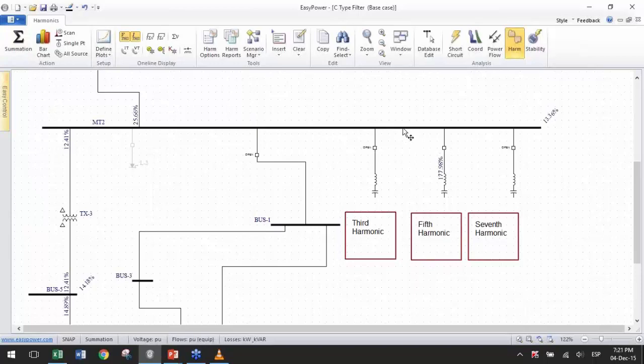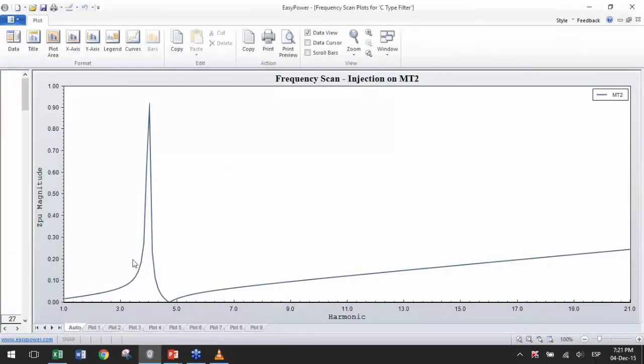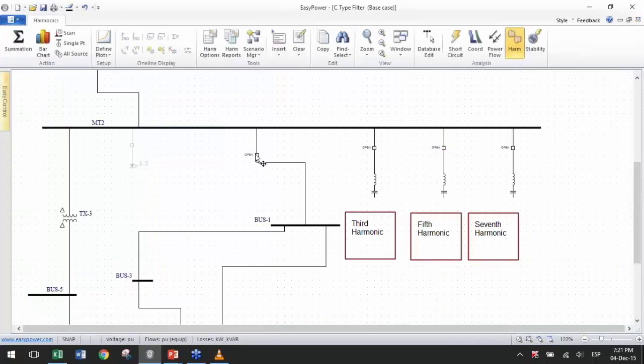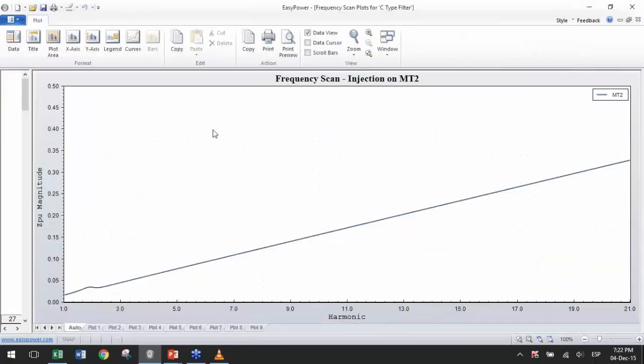For example, with the fifth harmonic filter, we have what is expected, a resonance around the fourth harmonic, the anti-resonance a little below the fifth. And let's check how our filter works. Now, this filter is working exactly as intended, because the resonance doesn't displace to the left. Because of the resistance, that resonance will attenuate very, very much. You can see that the system response is practically inductive. There's no resonance point, and that is important because that way the distortion goes way lower, especially for the second harmonic.